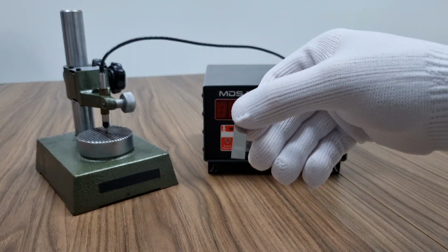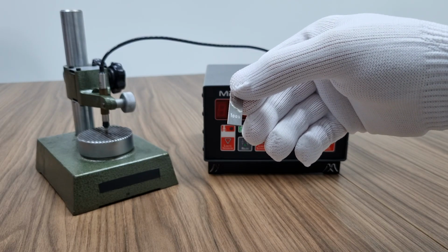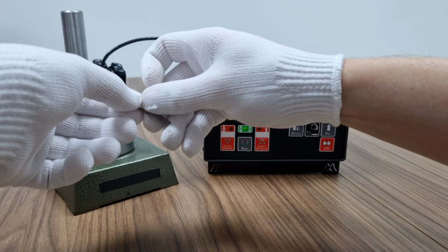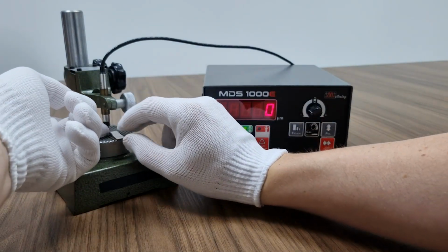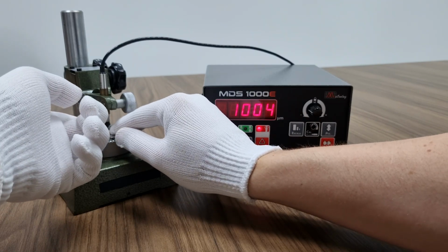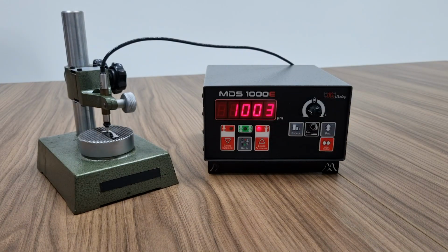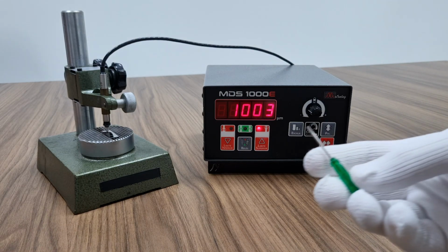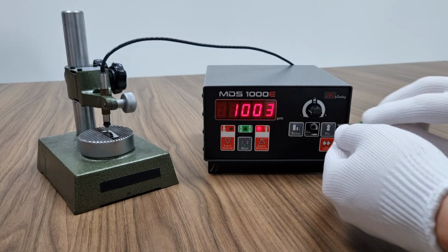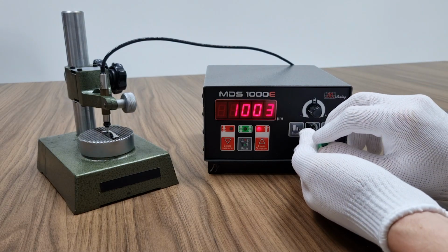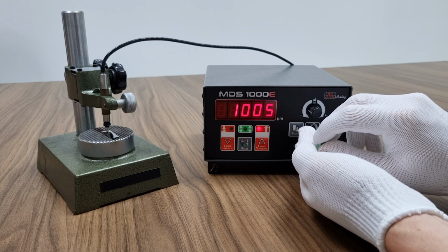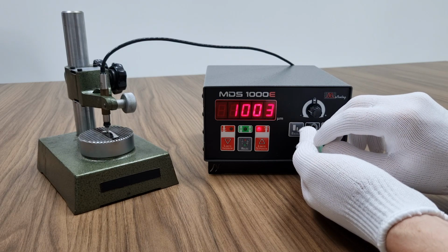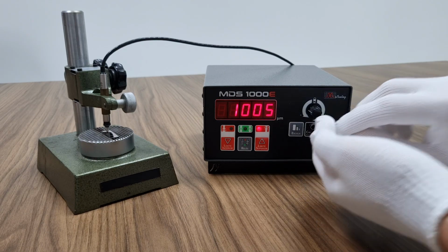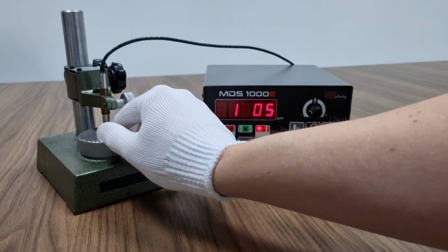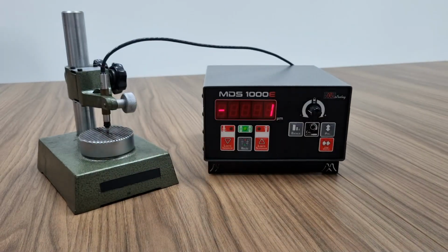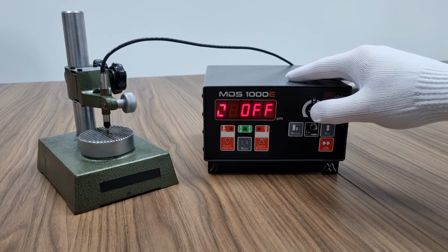Next, a calibrated standard block of known measure is inserted. In this example, a 1.005 mm block is used. The reading from the equipment is then observed. If deviation is detected, the cal setting must be modified using a small screwdriver. The procedure must be repeated iteratively until the two reference points are correctly indicated on the equipment.